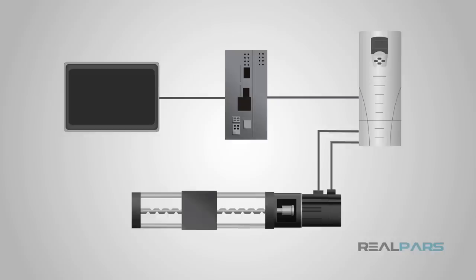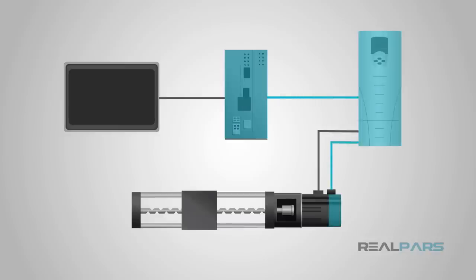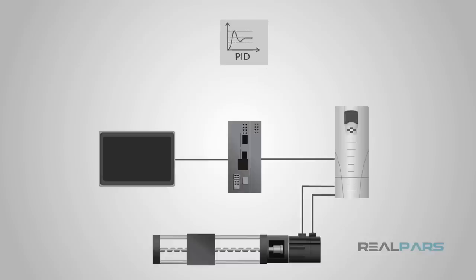One of the main differences between servo motors and stepper motors is that servo motors utilize a control loop, and this requires position feedback. The servo motor control loop uses feedback from the motor to help the motor arrive at a desired position and velocity. These control loops come in a variety of electromechanical types. The controller, or PLC software, will generally use a PID — Proportional Integral Derivative — control loop for servo motors to achieve accurate speed, acceleration, and distance.